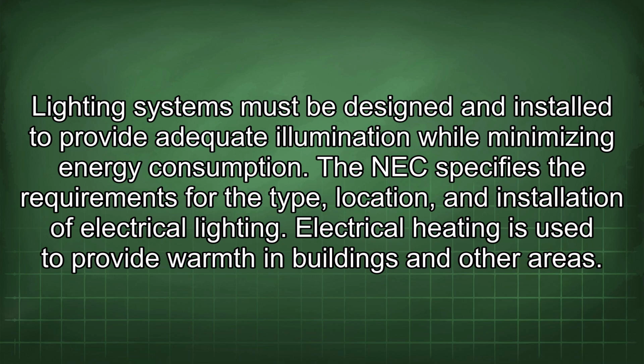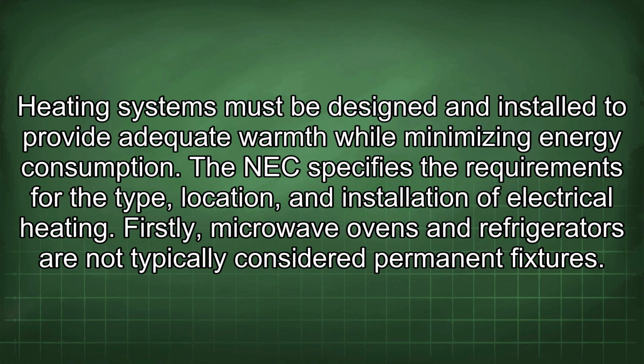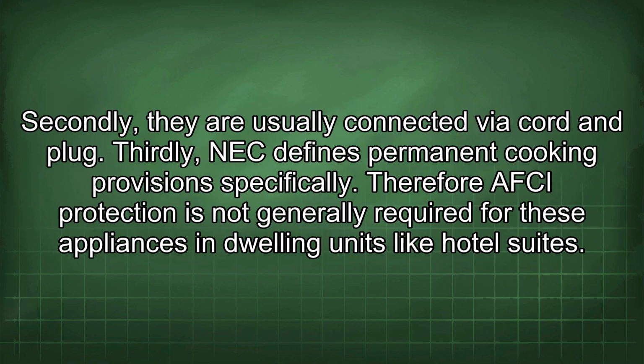Electrical heating is used to provide warmth in buildings and other areas. Heating systems must be designed and installed to provide adequate warmth while minimizing energy consumption. The NEC specifies the requirements for the type, location, and installation of electrical heating. Firstly, microwave ovens and refrigerators are not typically considered permanent fixtures. Secondly, they are usually connected via cord and plug. Thirdly, NEC defines permanent cooking provision specifically. Therefore, AFCI protection is not generally required for these appliances in dwelling units like hotel suites.